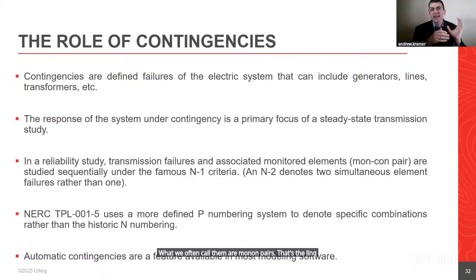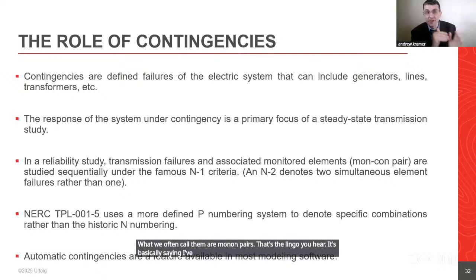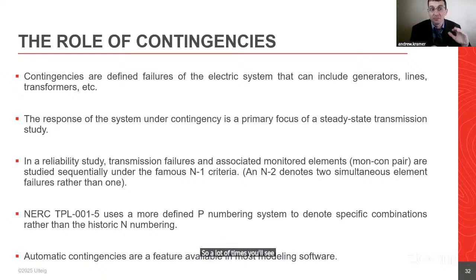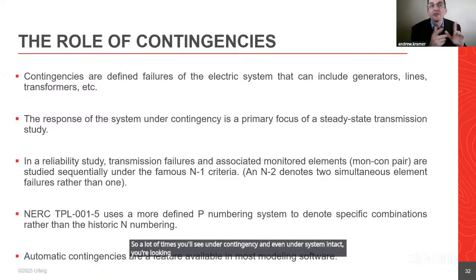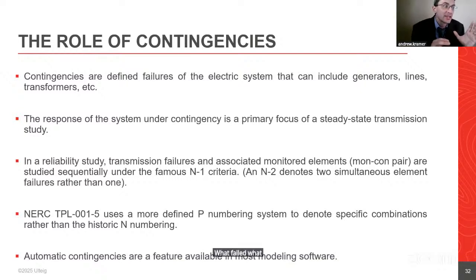It's basically saying I've got a contingency, something that's failure, and I'm going to look at a line to see if it's got a problem or thermal overload. That's the monitored element. A lot of times you'll see under contingency and even under system intact, it'll tell you thermal overloads. But specifically under contingency, you're concerned about these mon-con pairs. What's failed, and what are you looking at?